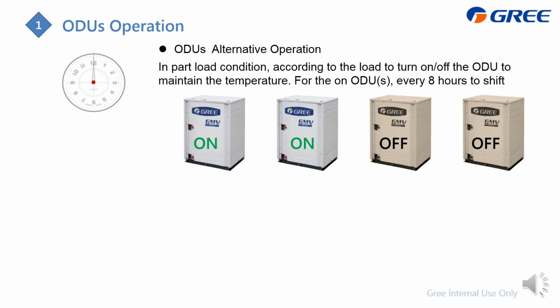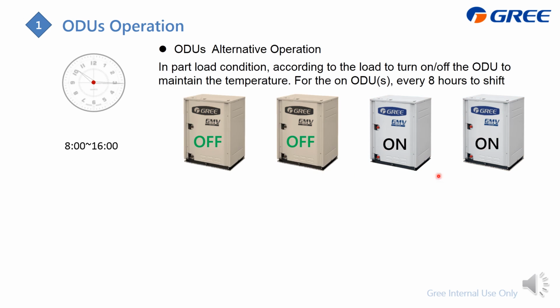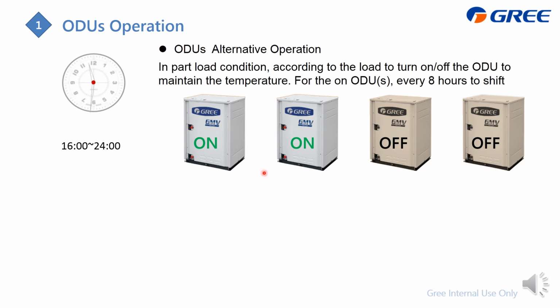Also the same, we have the alternated operation, which means in part load condition, according to the load, the outdoor units are turned on or off to maintain the temperature. And for the outdoor units, there are basically 8 hours to change. So for example, in this case, it just requires 2 outdoor units to turn on. The other one just rests. So it operates first for 8 hours, then for the next 8 hours we go to this 2, and then operate another, and we go back to this 2.